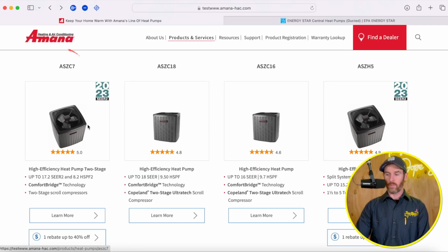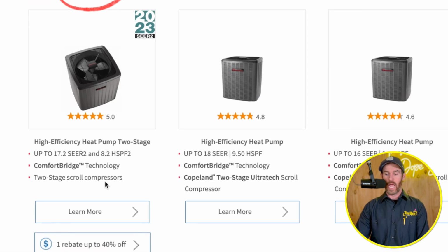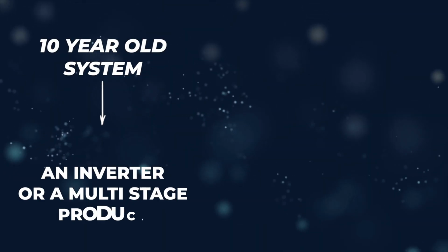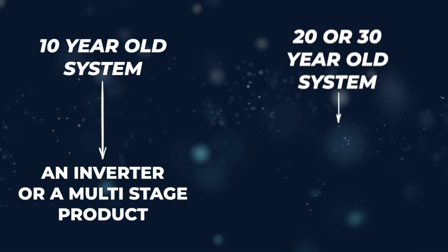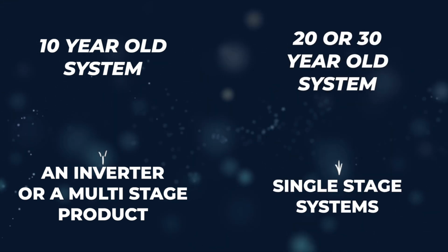Now if we jump up to this ASZC7, the only difference between these two systems is it has a two-stage scroll compressor. The difference between a two-stage and a single-stage system is kind of what it sounds like. A single-stage system is either on or off. If you have an air conditioner right now that's 10, 20, or 30 years old, a 10-year-old system could still be an inverter or multi-stage product, but most 20 and 30-year-old systems are single-stage systems. Especially if you're living in a house where you haven't replaced the HVAC yet and it's original to the home, like a 15-year-old system, most builder-grade products were single-stage.